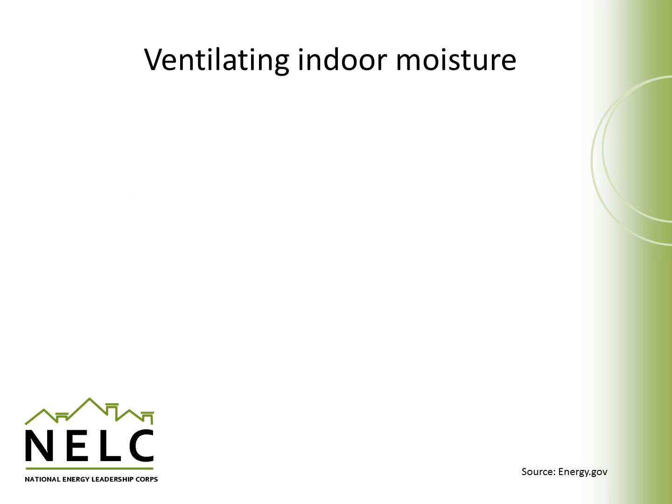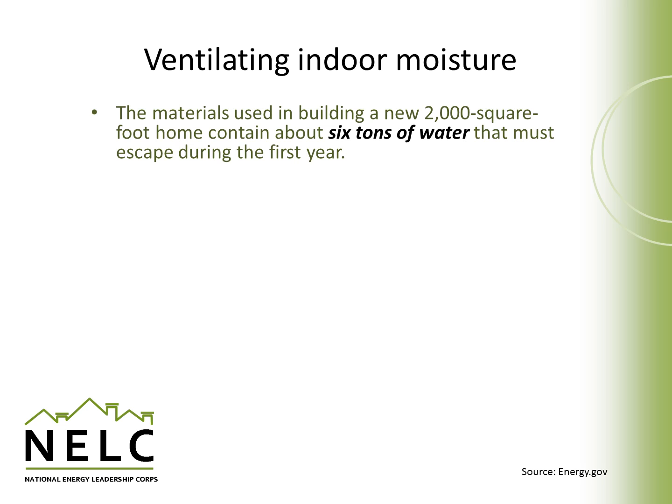Ventilating indoor moisture is another important reason to make sure there's a significant amount of ventilation in our homes. The materials used in a new building — for example, a 2,000 square foot home — can contain up to six tons of water that must escape and evaporate over the first year, particularly in the wood framing and drywall materials. If the house is too tight, it will take longer for that to evaporate and can even cause problems during early occupancy.